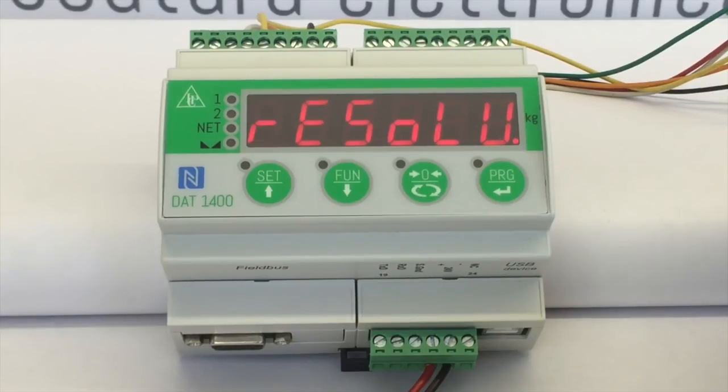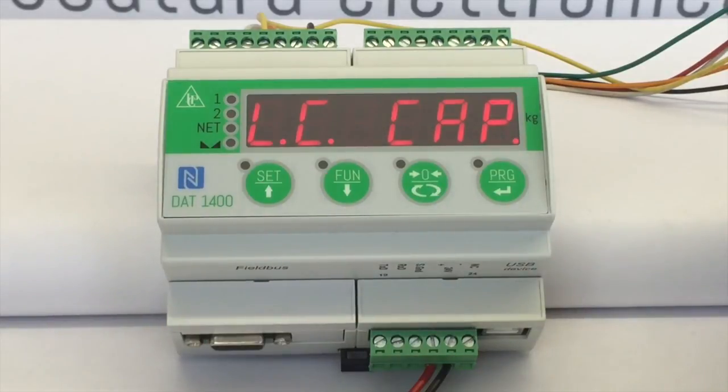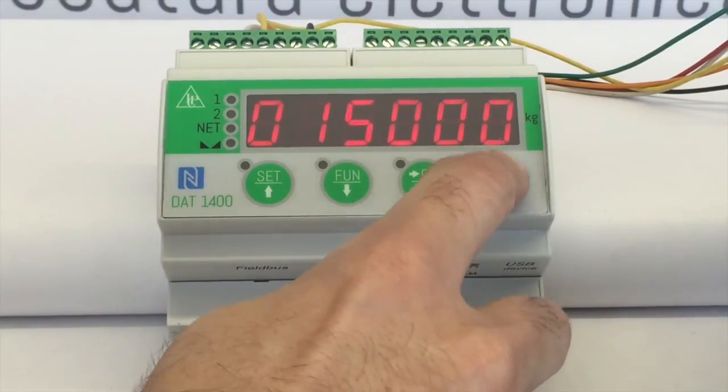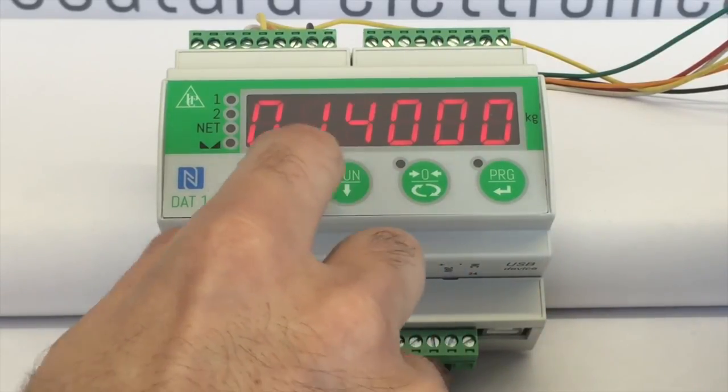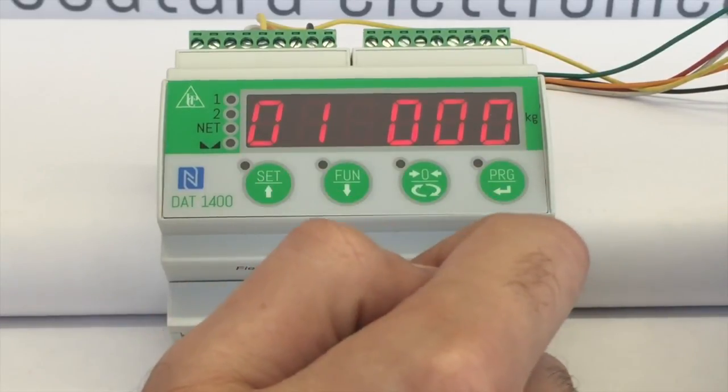By scrolling with SET and FUN, let's set the TOTAL SYSTEM CAPACITY, LC CAP, which is the sum of the capacities of each individual load cell in the system. For example, 10,000 kg. Press PRG again to select units, tens or hundreds and set the desired value with SET and FUN. To confirm, hold down PRG for 2 seconds.